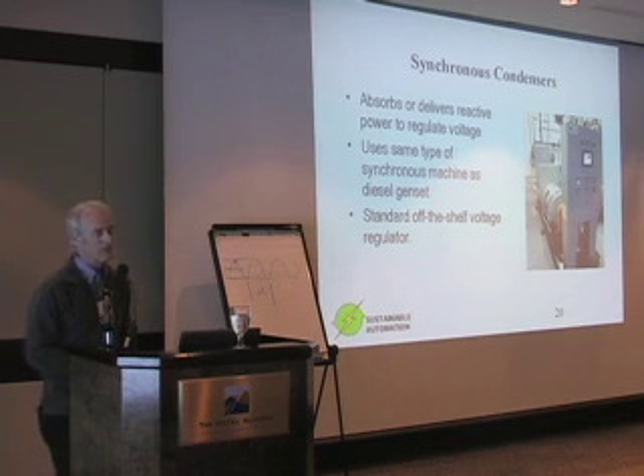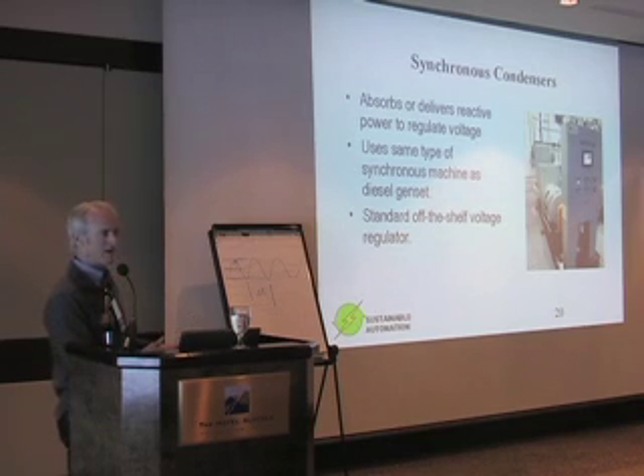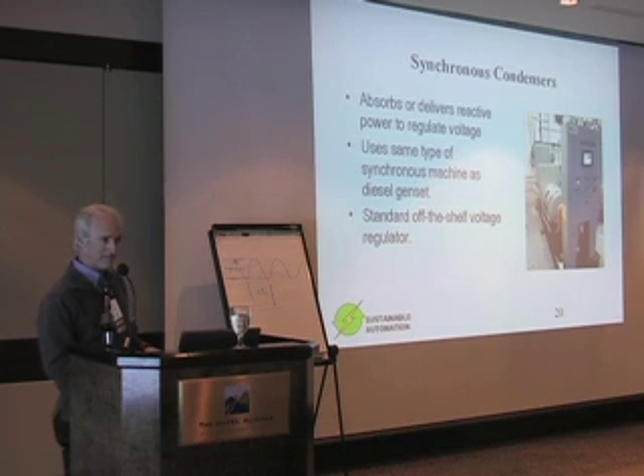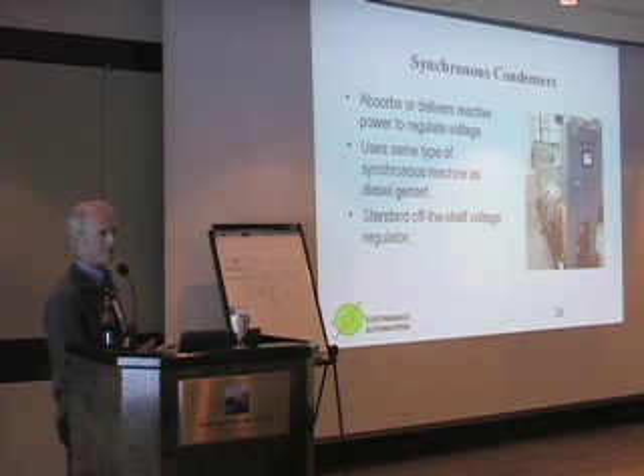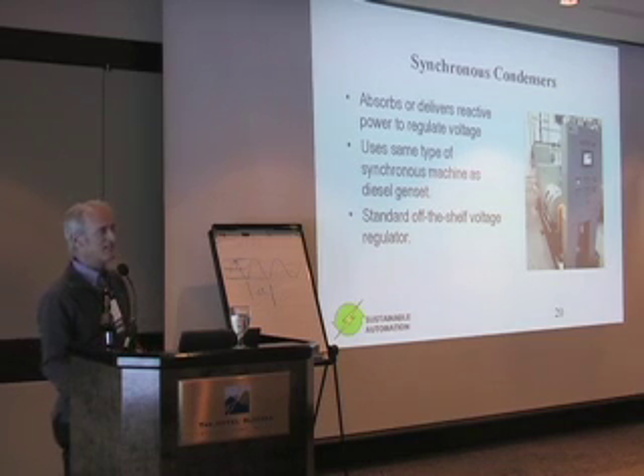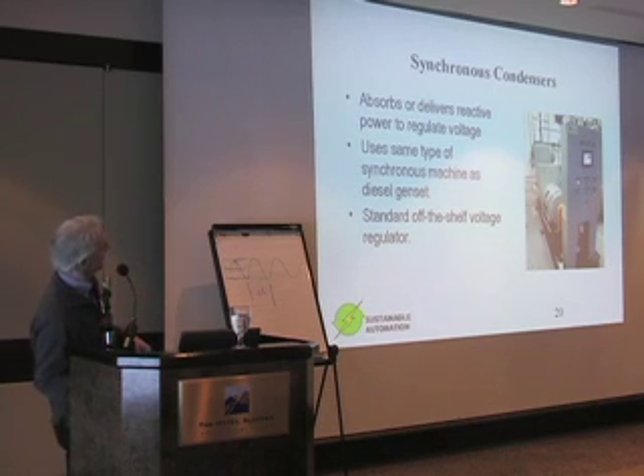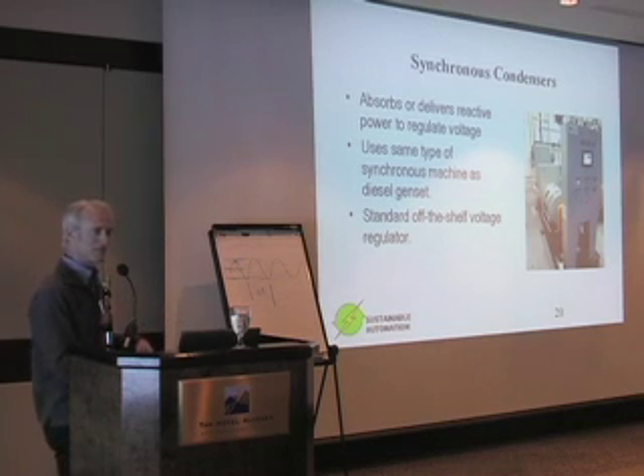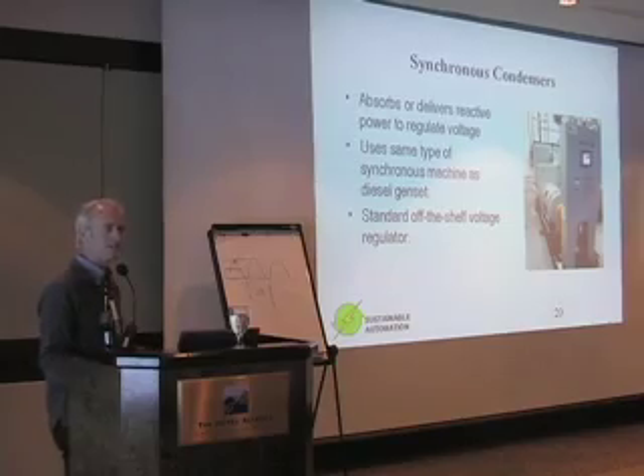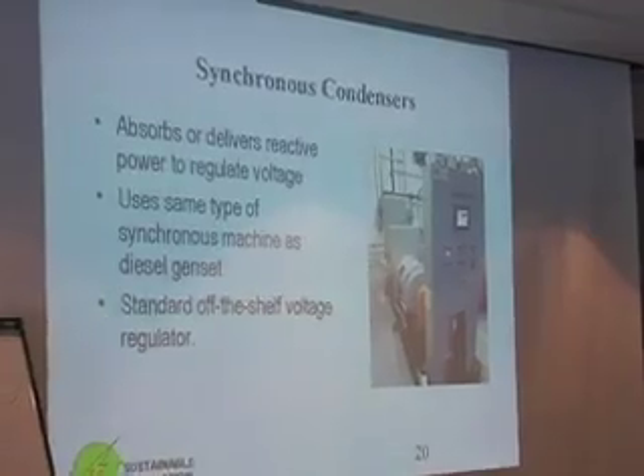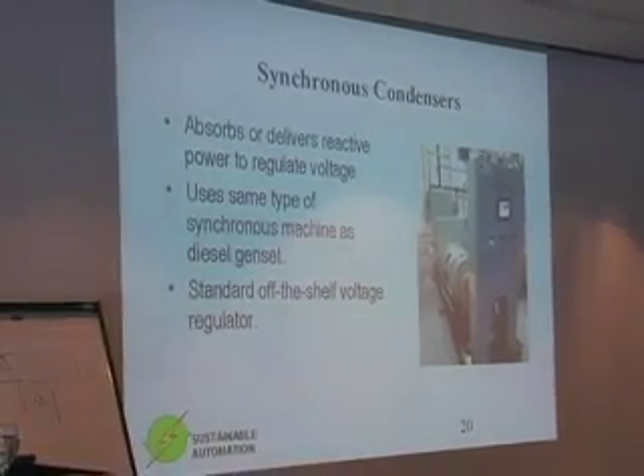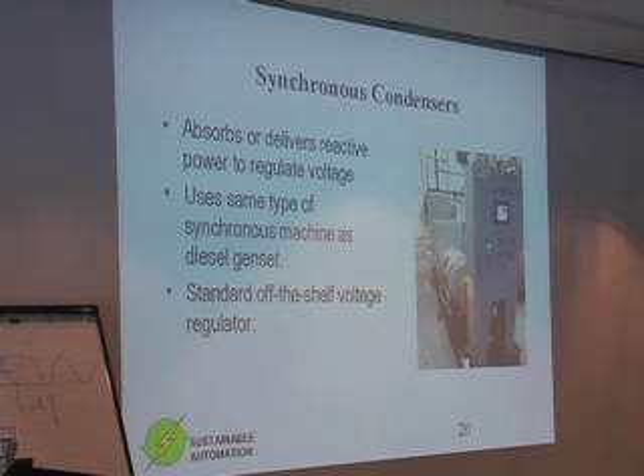Synchronous condensers we touched on a little bit earlier. Now we're getting to the other power balance that needs to be achieved, and that is the reactive power balance. A synchronous condenser is essentially a synchronous machine just like you would find on a generator set, without the engine, without the prime mover. There's a small pony motor that brings it up to speed so that it can synchronize with the grid. But as soon as it's synchronized, the pony motor shuts off, and it's just spinning on the grid, and it's got a voltage regulator connected to the synchronous machine, just like any genset would. And you control the supply or absorption of reactive power by biasing the voltage regulator set point, just like you do on a standard diesel genset.